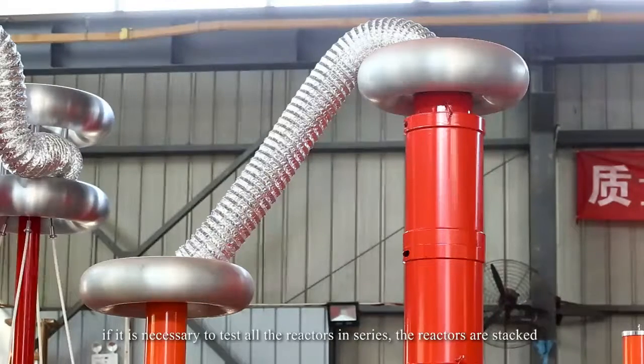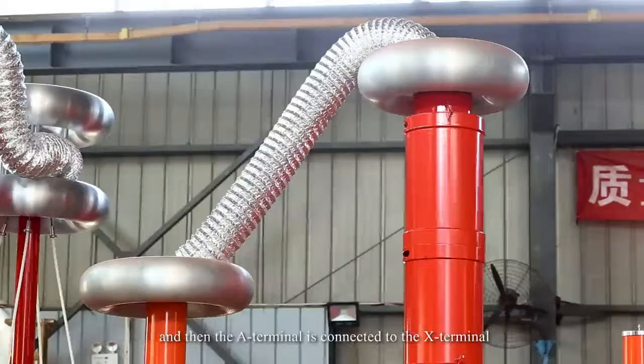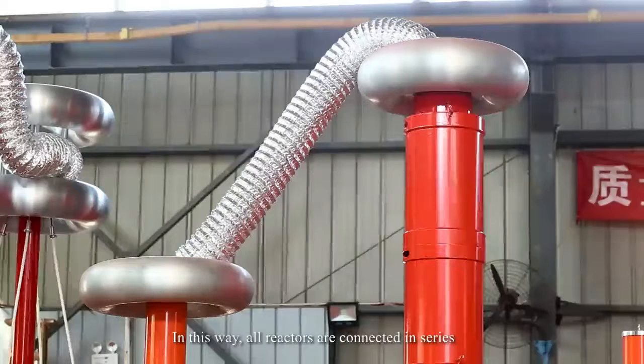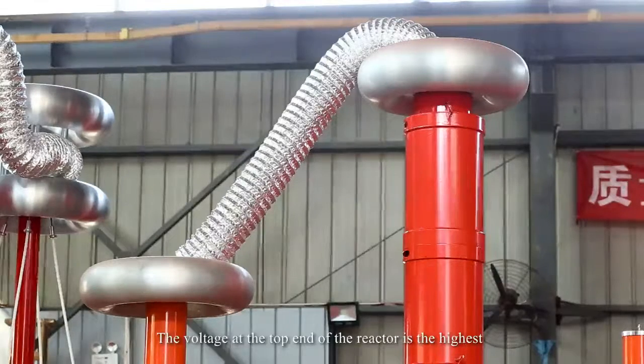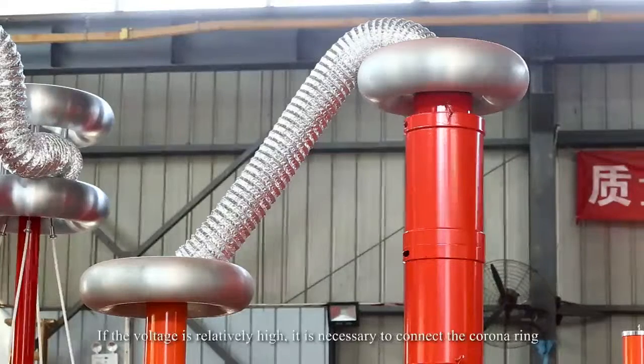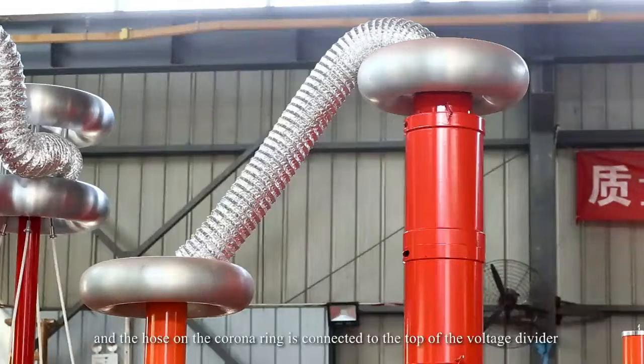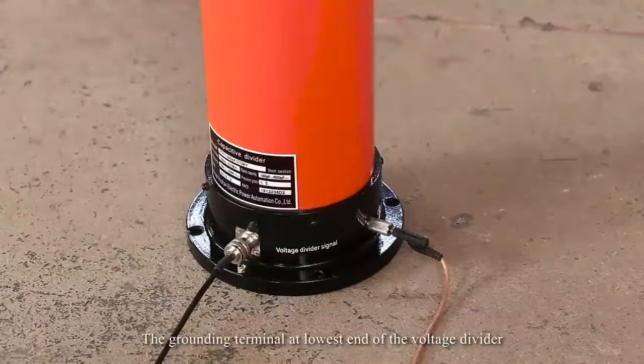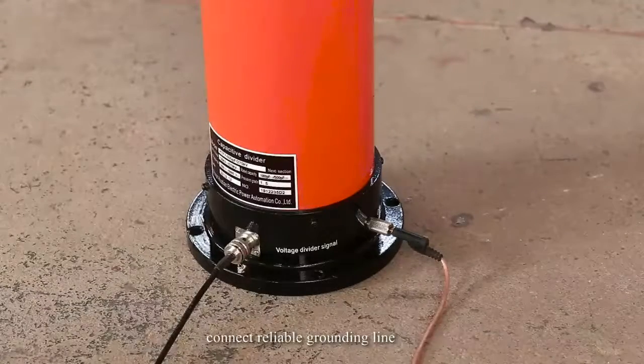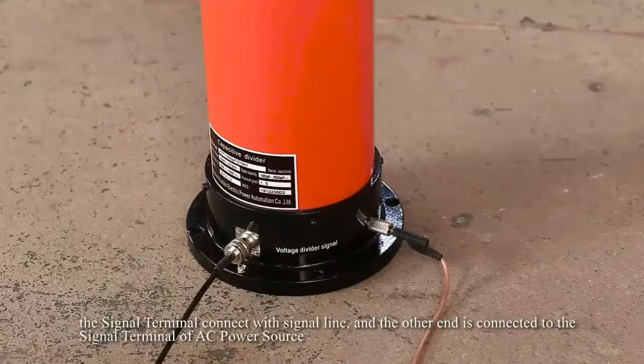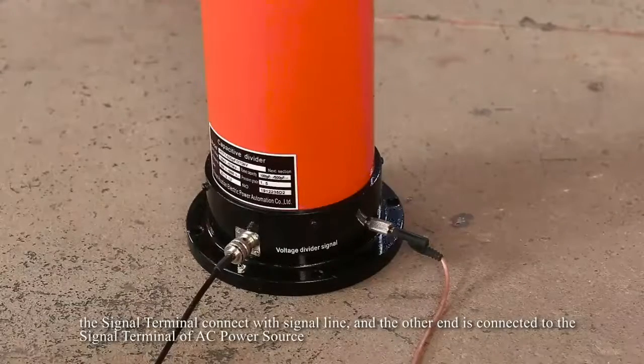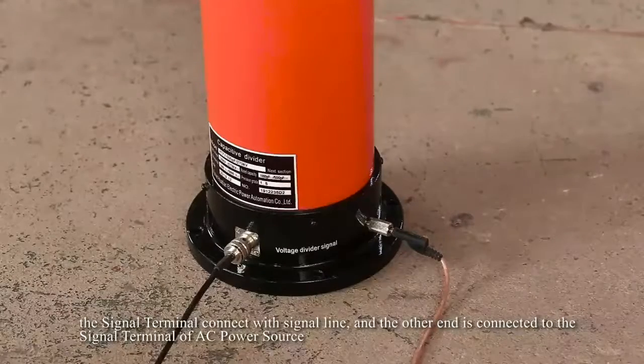If it is necessary to test all the reactors in series, the reactors are stacked, and then the A terminal is connected to the X terminal. In this way, all reactors are connected in series. The voltage at the top end of the reactor is the highest. If the voltage is relatively high, it is necessary to connect the corona ring, and the hose on the corona ring is connected to the top of the voltage divider. The grounding terminal at the lowest end of the voltage divider connects to a reliable grounding line. The signal terminal connects with a signal line, and the other end is connected to the signal terminal of the AC power source.